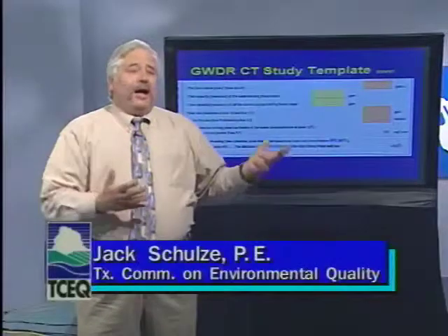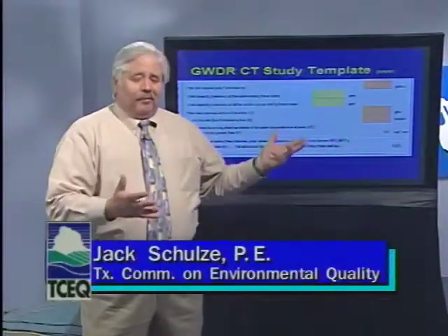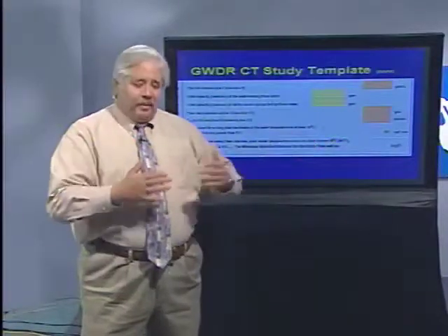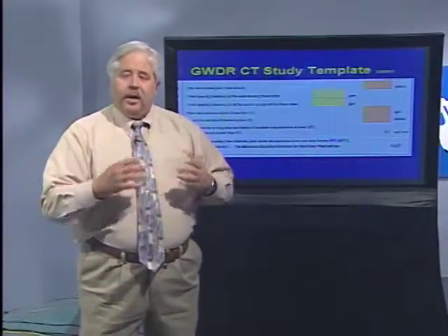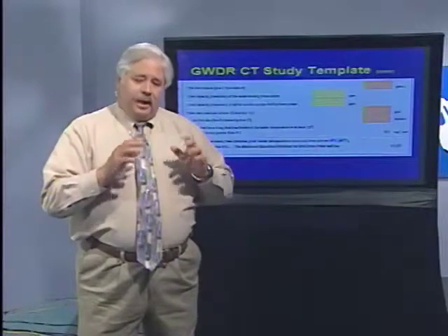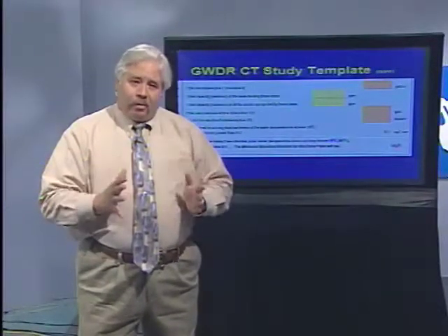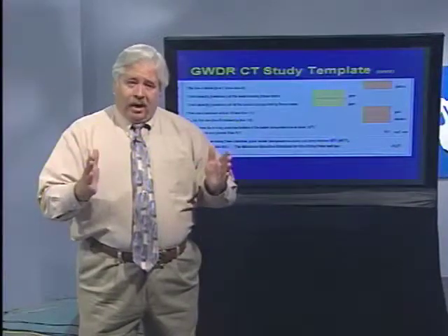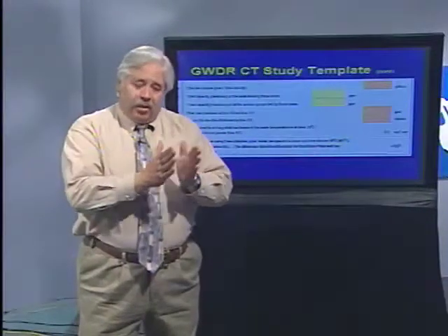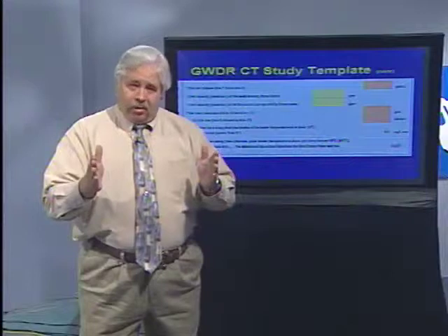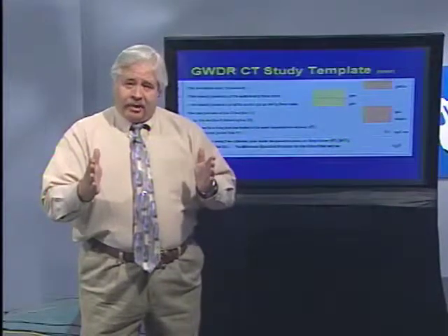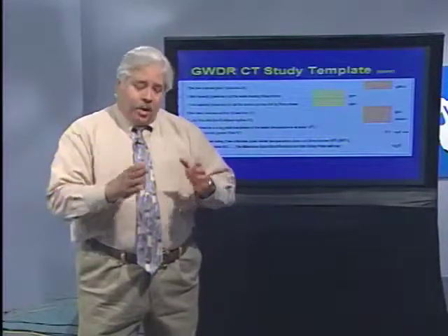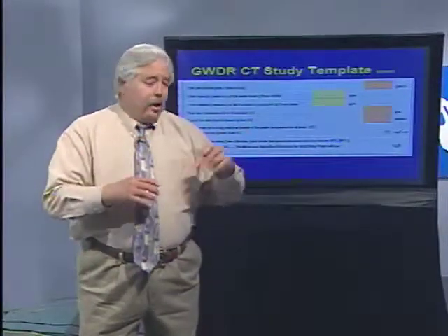Okay? Now, if I've got large capacity service pumps and I've got this small well pump, how does input ever equal output? Because the evaluation that you guys do for 4-log viral is based on a 4-hour compliance period, you're in compliance as long as that number doesn't drop below your minimum specified residual for more than 4 hours. You haven't violated the rule. We're looking at a peak hour period.